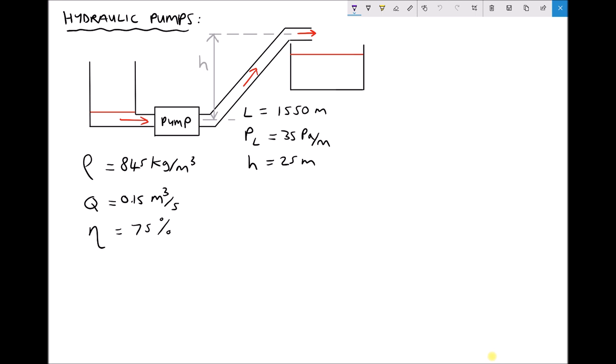In addition, the pump needs to elevate the fluid through a maximum height of 25 meters. If there was a larger quantity of fluid in the lower header tank, that would actually assist the pump by providing back pressure. However, we're going to assume the worst case scenario and assume that the lower tank is almost empty, so the pressure behind the pump is negligible compared to the pressure downstream of the pump.